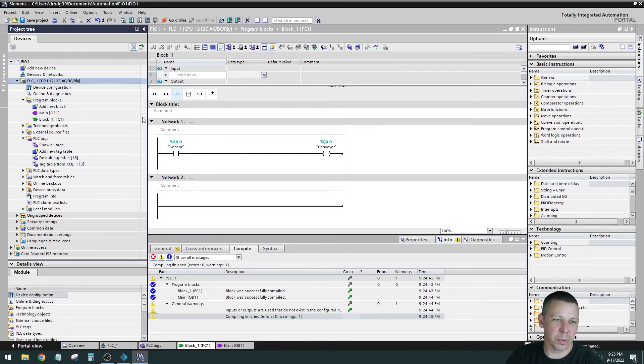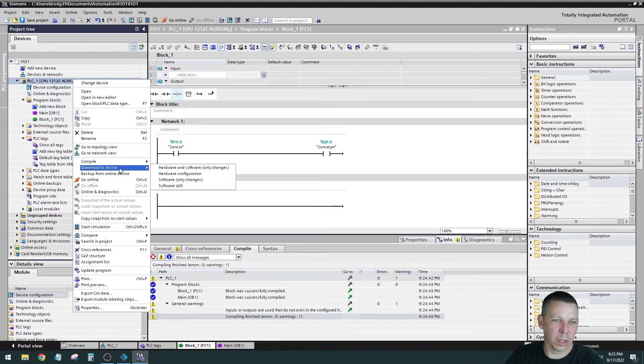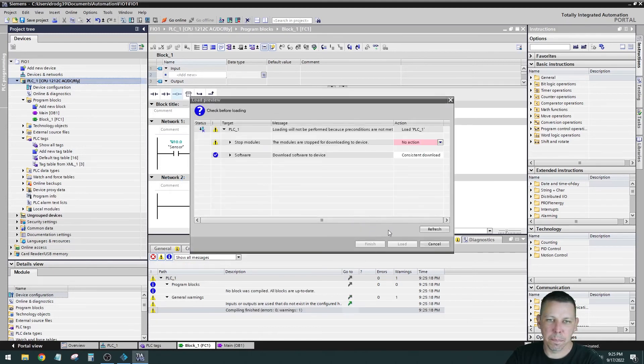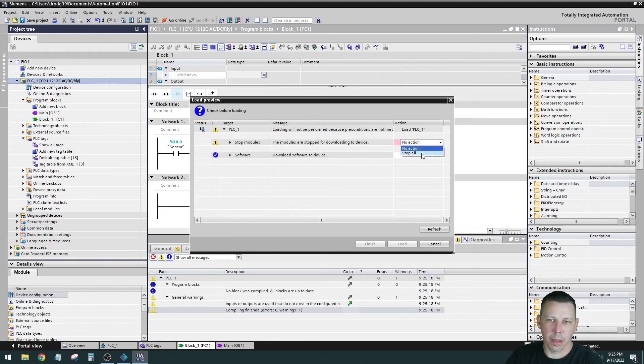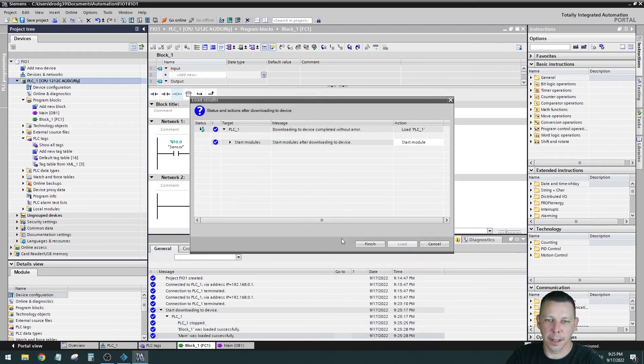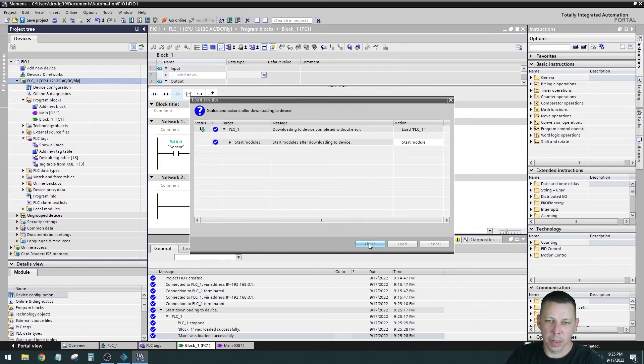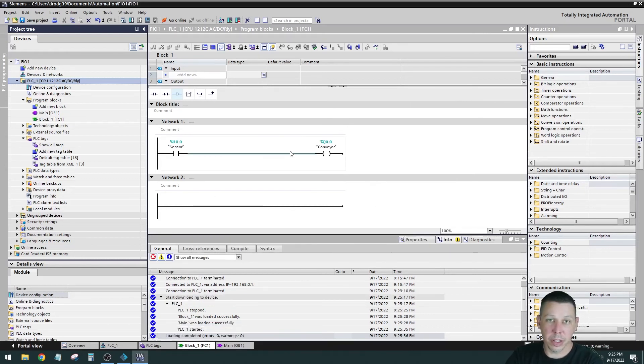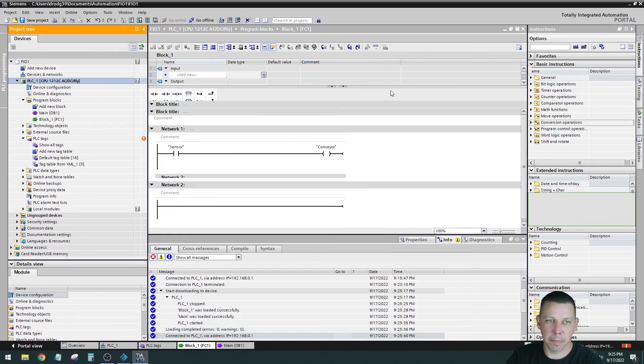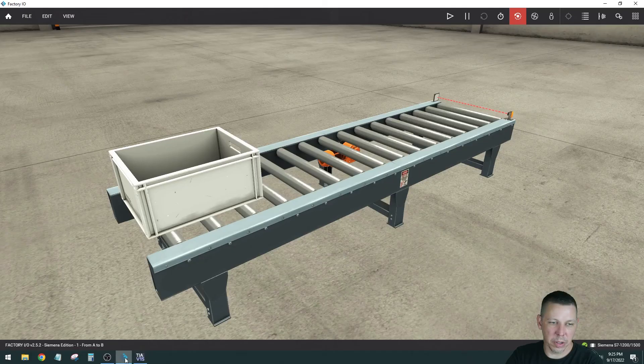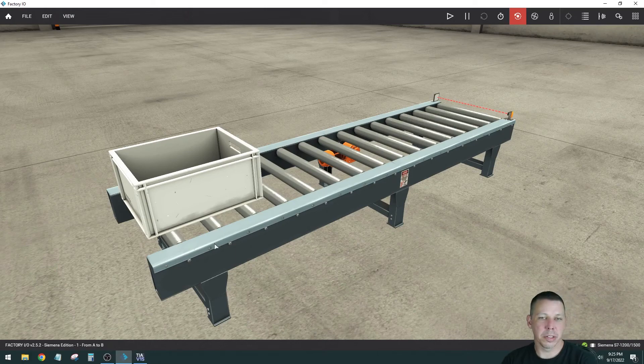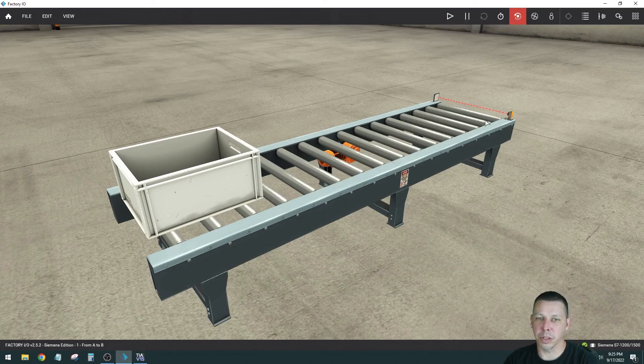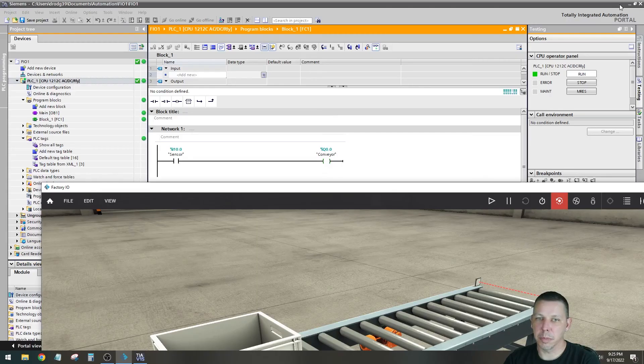Now we are going to right click and go to download to device, software only changes, and we're going to stop all. It just takes the processor out of run mode while we're loading it. And then it says, what do you want to do? Basically after this and you want to put it back in run mode. So let's go back and remove it. And now to see this in real time, we can click the glasses up here and you'll see that the conveyor is receiving the signal to run. So let's go back to factory IO. The reason it's not running yet is because you have to play on your simulation here. So now when I hit play, it should run until it breaks this beam. And when it breaks the beam, it should stop.